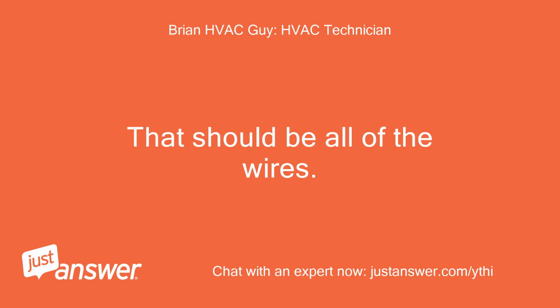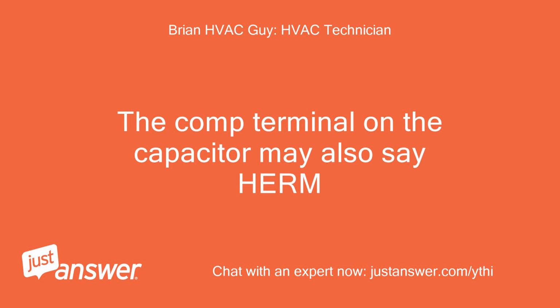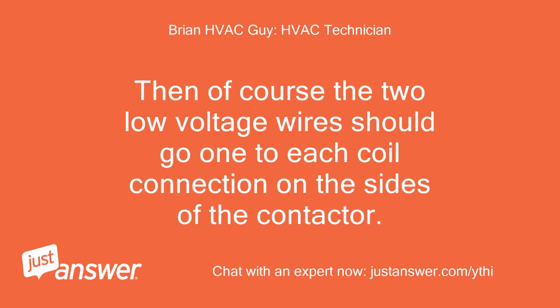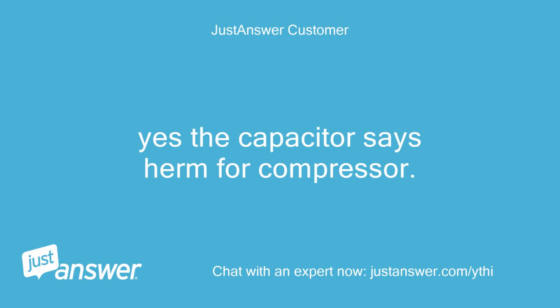That should be all of the wires. The comp terminal on the capacitor may also say HERM. Then of course the 2 low voltage wires should go one to each coil connection on the sides of the contactor. Yes, the capacitor says HERM for compressor.